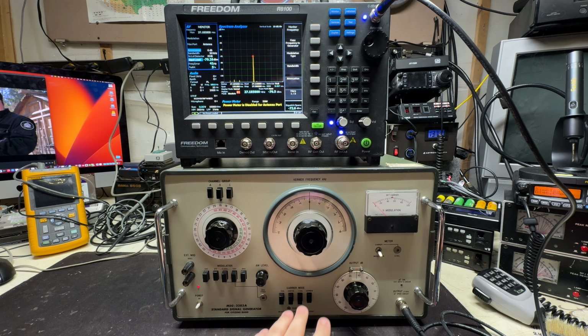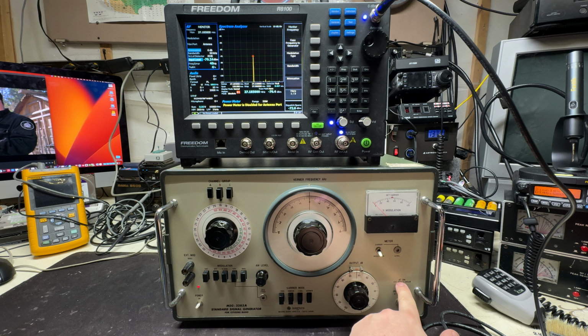This isn't a transmit into test set. It does have some protection built into it. The attenuator attention light will turn on with an external input of 300 milliwatts. You really don't want to transmit into this. That's a big no-no. So you have to be extremely careful to not do so. It does have some protection, but it's still not good to transmit into it. So, all right. Well, let's take a look and see how close we are on frequency. So I'm going to just go ahead and click the center button here.